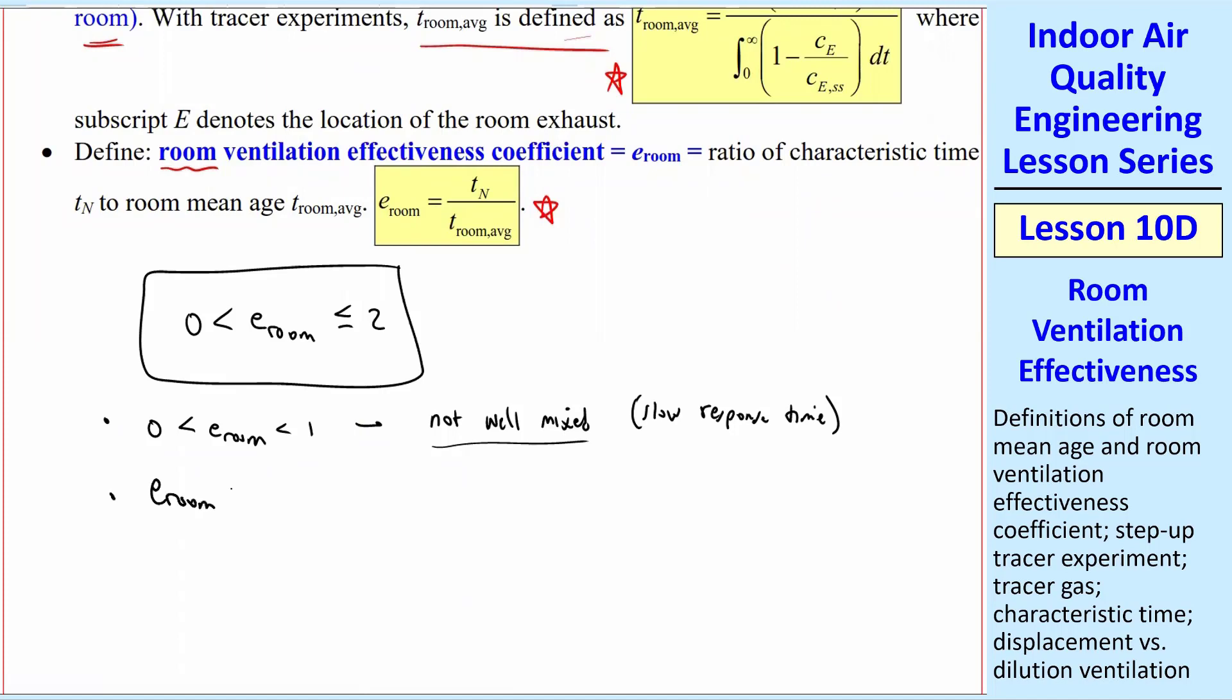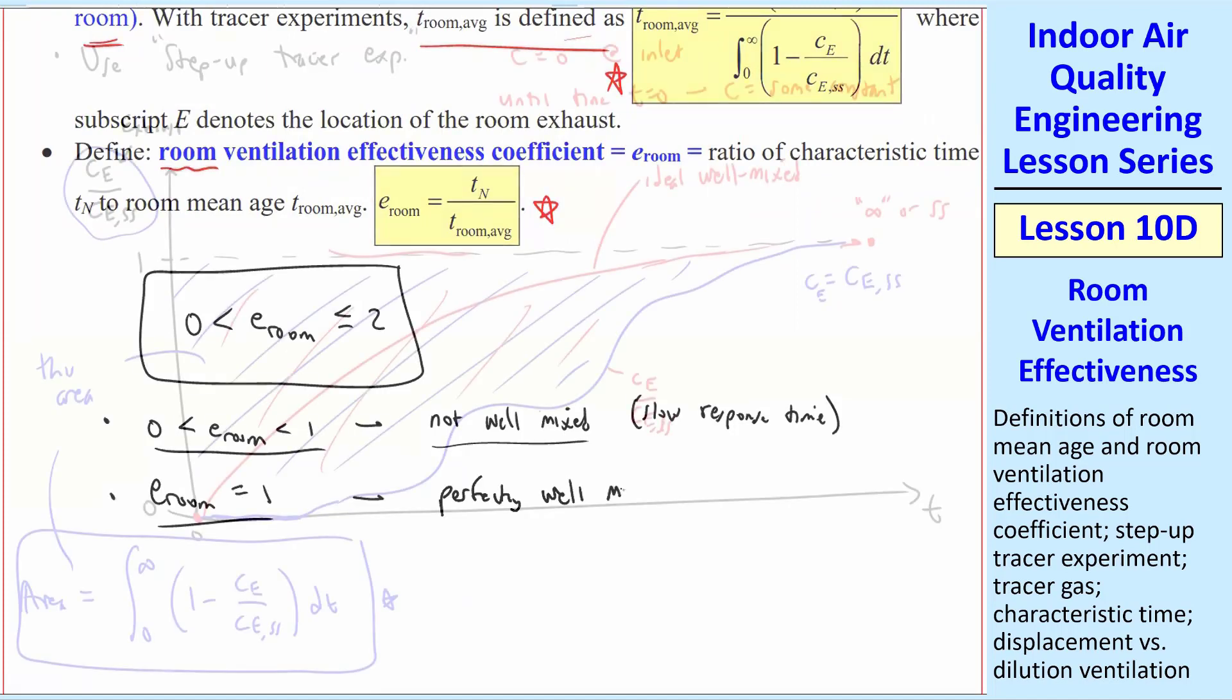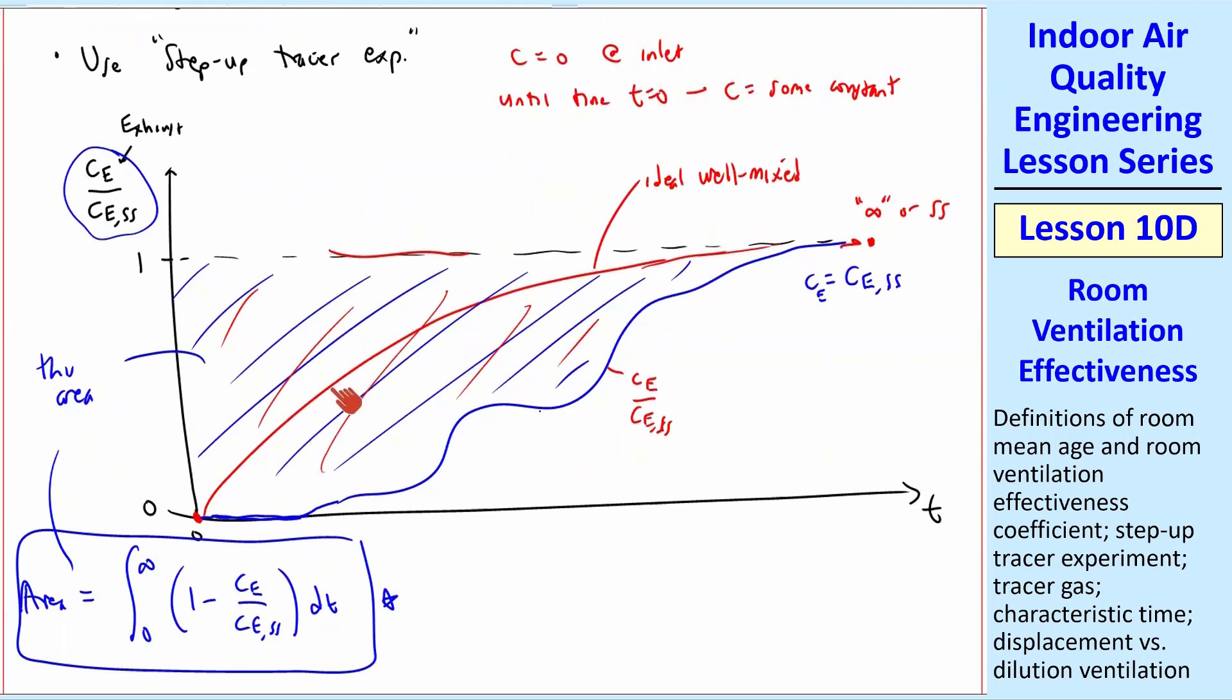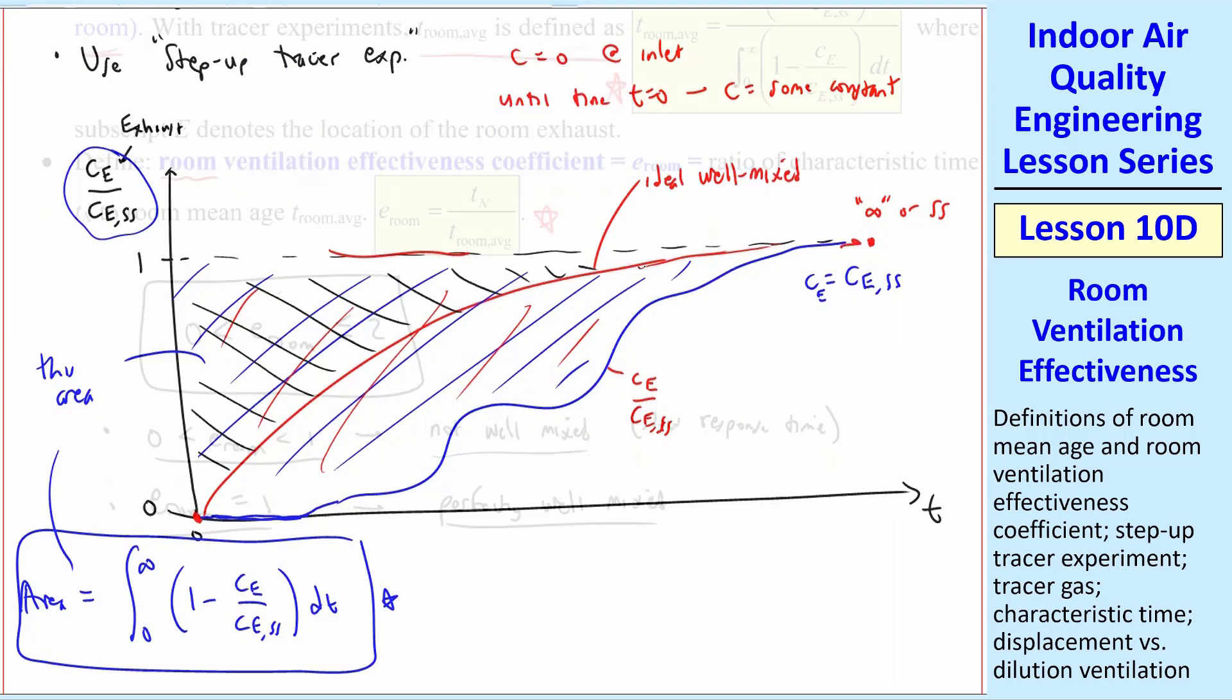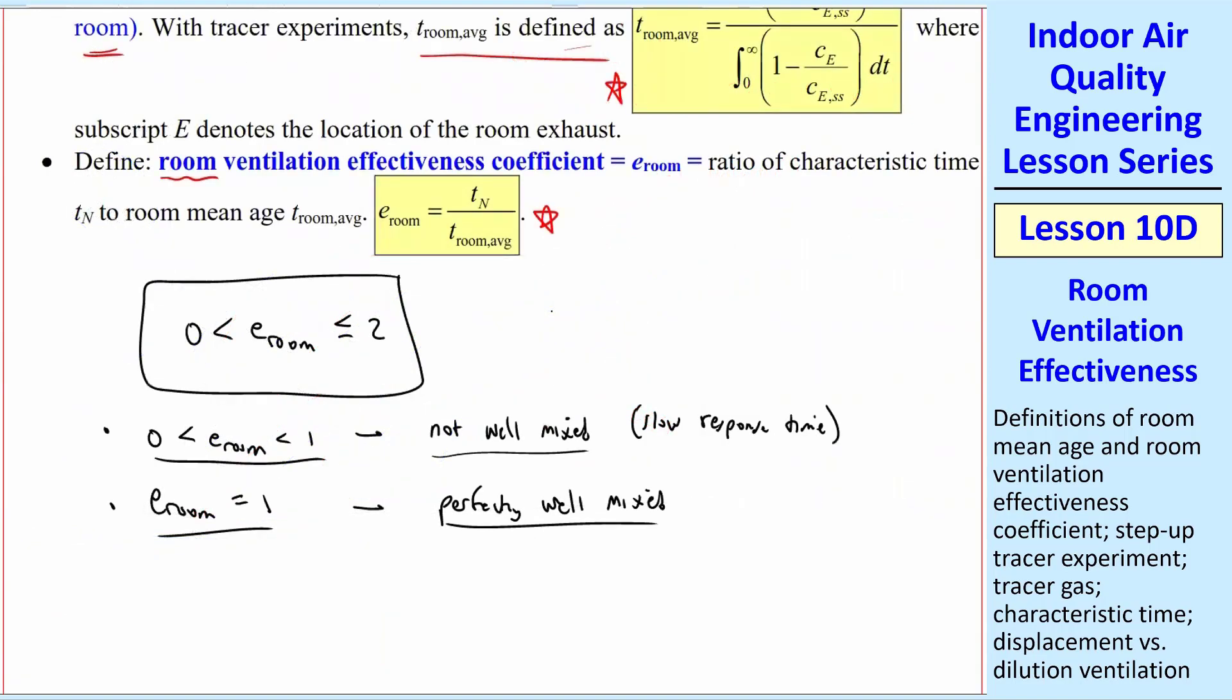If E room is equal to 1, this would be perfectly well mixed. So if you take this red curve here, which is the ideal well mixed case, and do the integral, it would be the area here above that curve. And we have an equation for that. If you go through the math, which I have done, you will find that E room is exactly 1, ideal dilution ventilation.